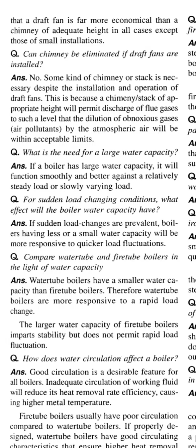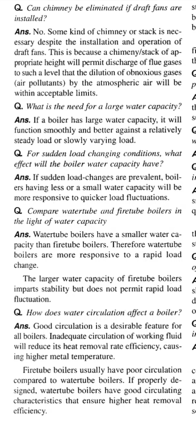Question: compare water tube and fire tube boilers in the light of water capacity. Answer: water tube boilers have a smaller water capacity than fire tube boilers. Therefore, water tube boilers are more responsive to a rapid load change. The larger water capacity of fire tube boilers imparts stability but does not permit rapid load fluctuations.